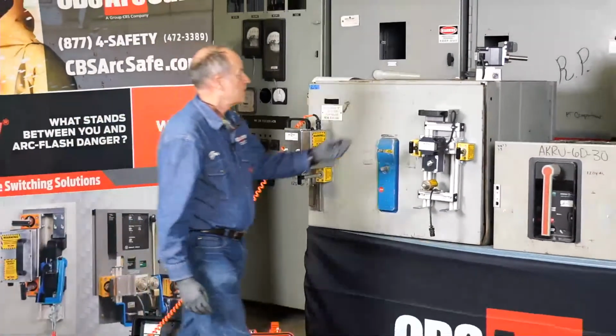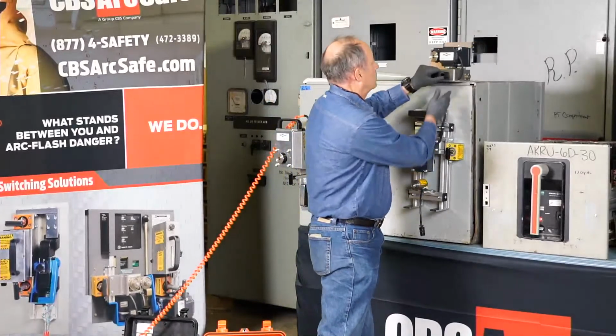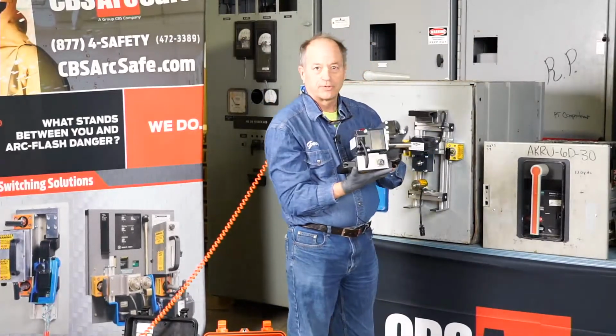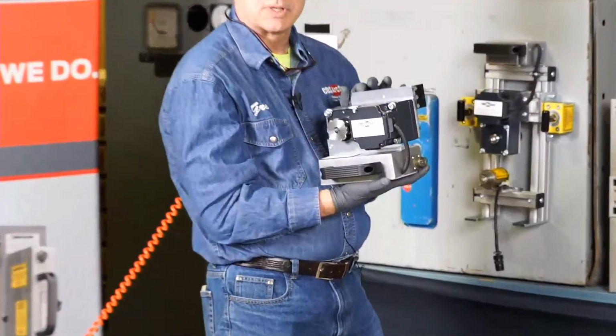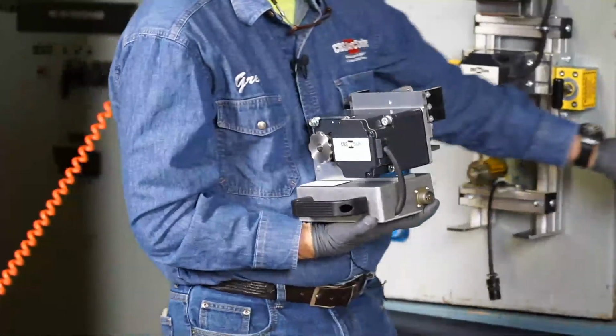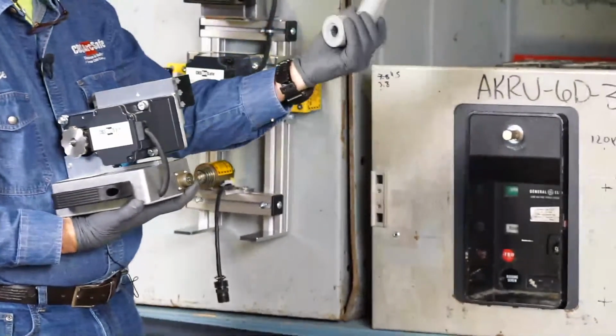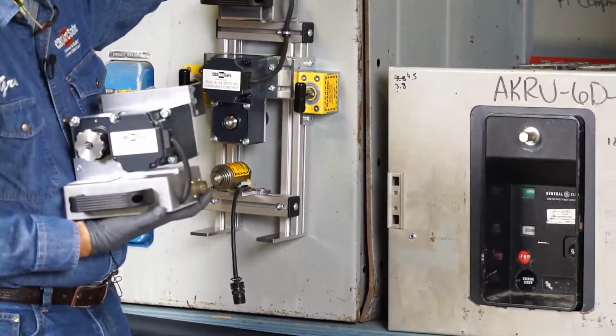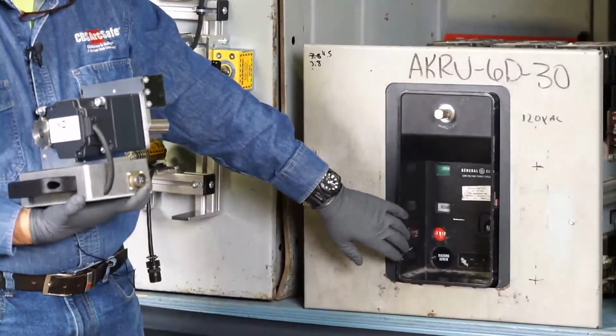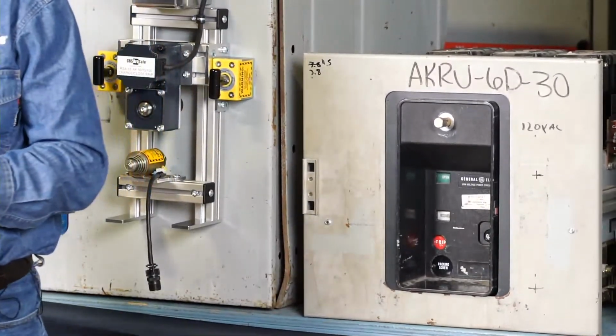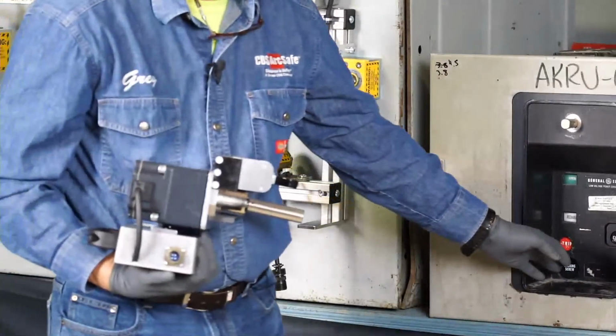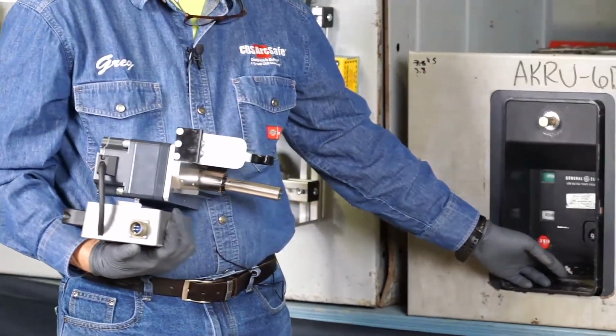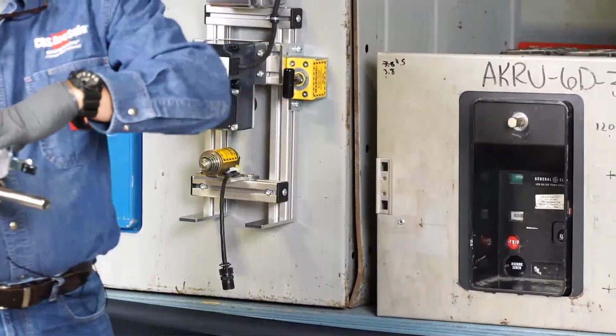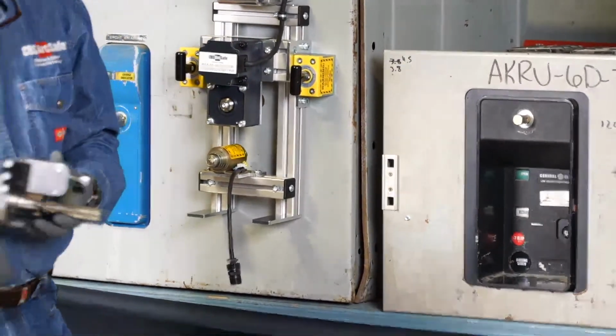Now, just on the side, here's the remote racking system for the GE AKR for the standard face. You have to take the handle off so you can gain access to the racking port. This one simply clips into the trip button once you've got the racking screw exposed, and it fits nicely inside the face.